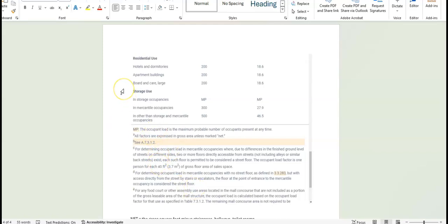And so if this literally is just going to be for bringing parts in, bringing parts out to go into a different facility to install on the cars, then I'm going to guess any one time the maximum probable number of people in there is probably going to be 10, to be very honest with you. I know it's a bigger building. It's 5,000 square feet something. But talking with the clients, 10 is going to be the maximum probable number of occupants.